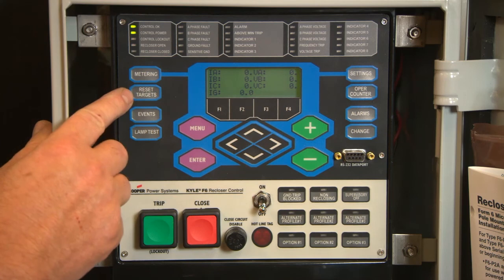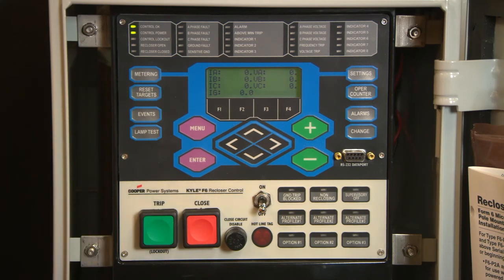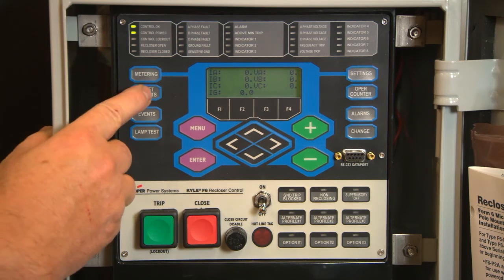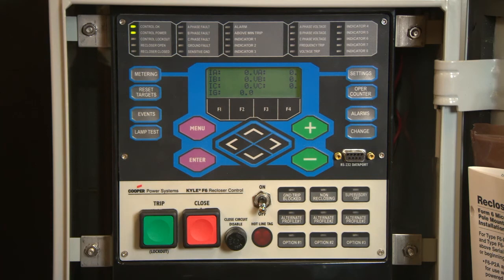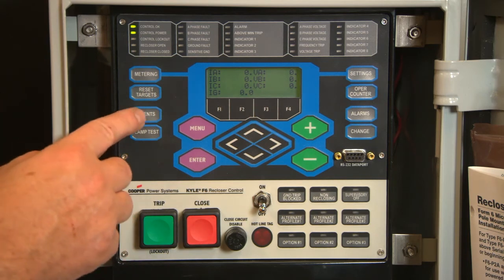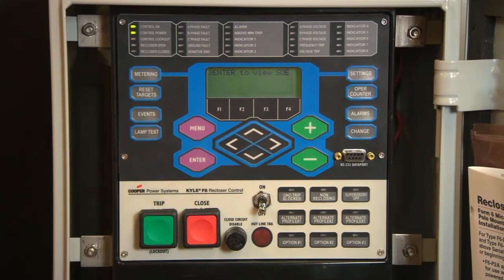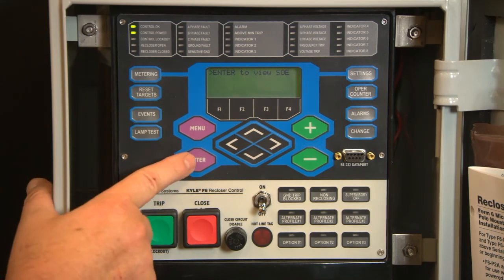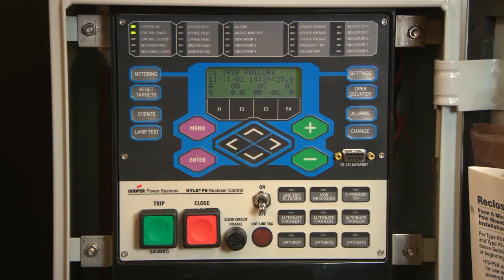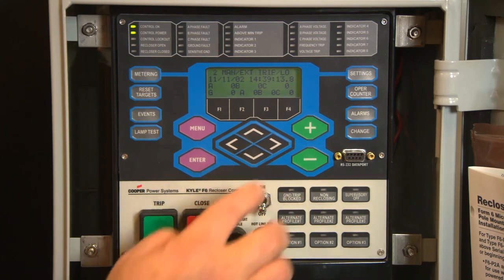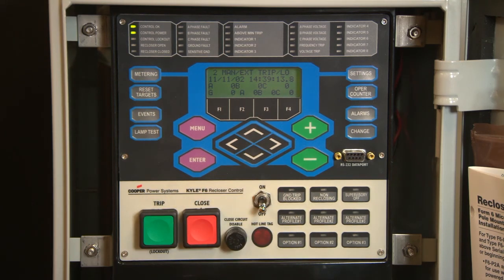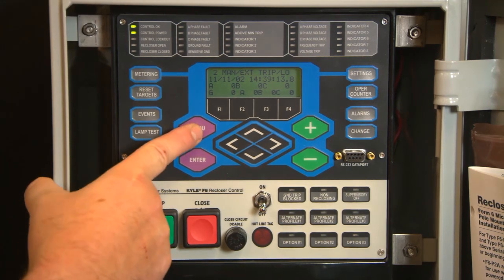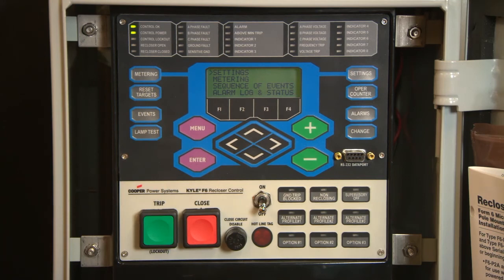Target reset. If the control trips out under a faulted condition and you wish to reset the targets before closing, press this button. Pressing this button will clear all unused items. Events. By pressing the Events button followed by the Enter button, the most recent trip will be displayed. Using the arrow keys, you can now scroll through subsequent trips, up to 40 operations. The display screen shows a manual trip to lockout. No currents are displayed. Press the Menu button to back out of this selection and return to the main menu.